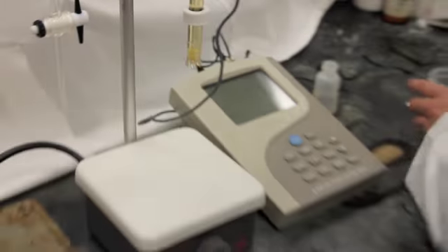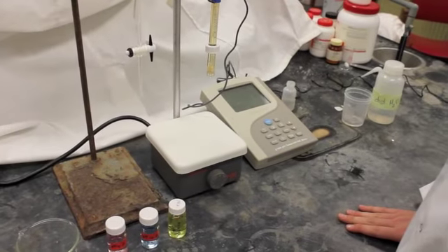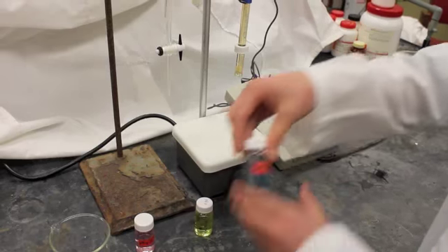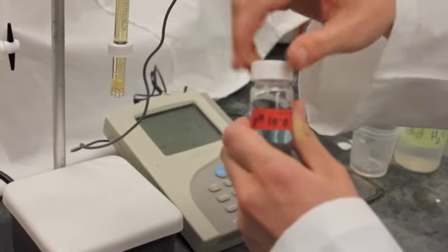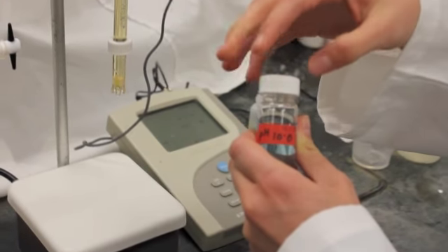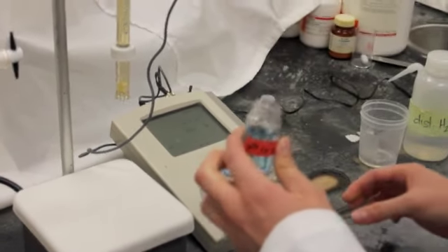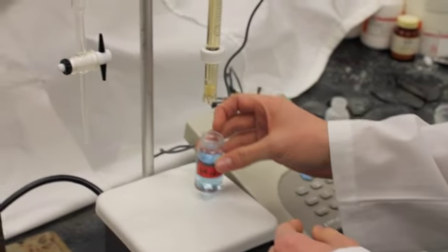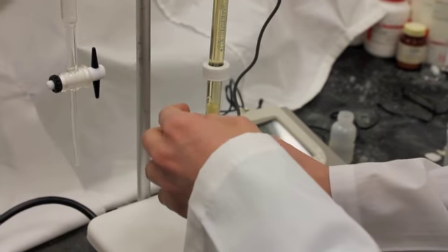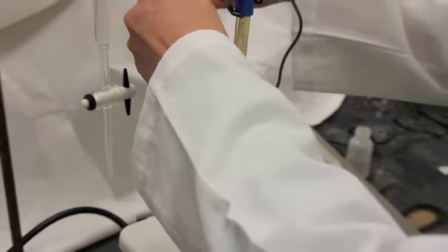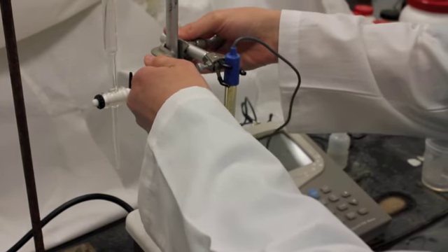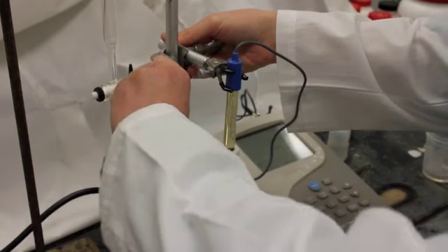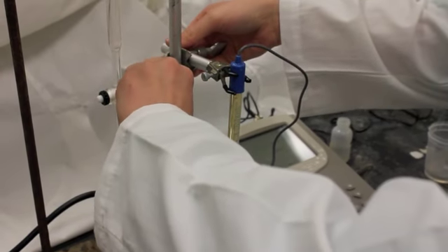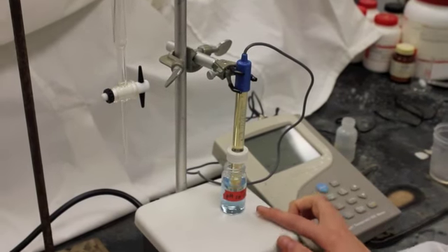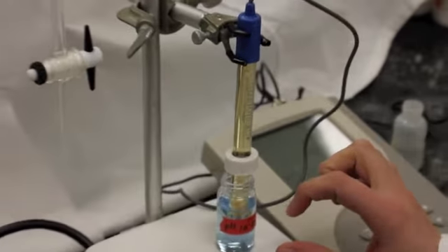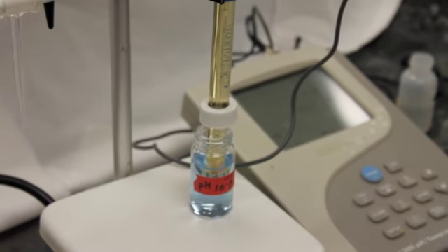Okay. And then you choose one of your reagents. You can start with the highest, so pH 10. And this will standardize the pH meter with a standard curve of 2 points. So this is the first point, and you can lower your pH meter into the reagent. And screw it back on so it's stable. And you should not have the probe touching the bottom. It should just be suspended about like a centimeter under the water.